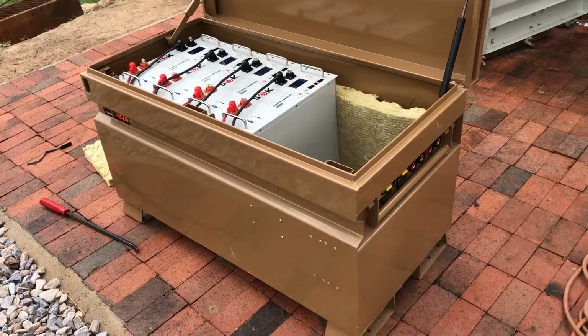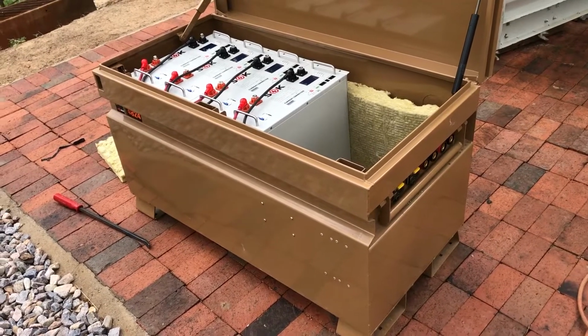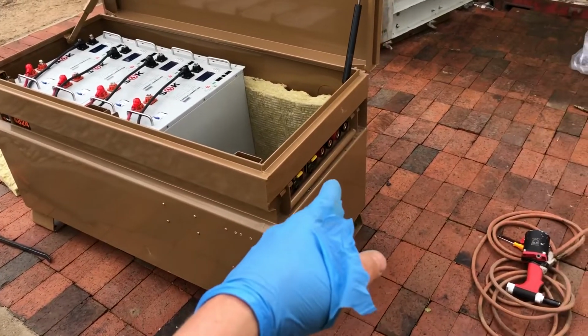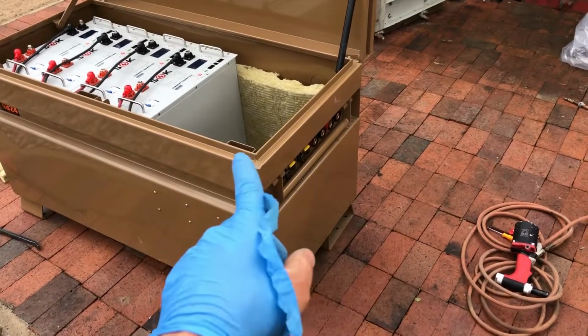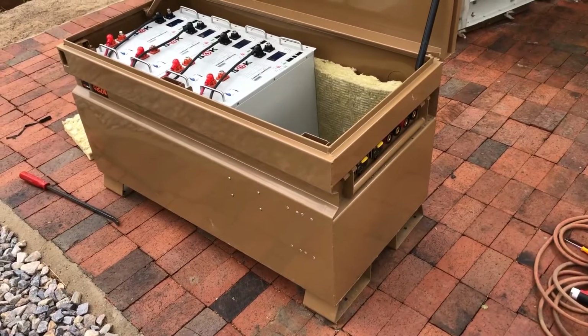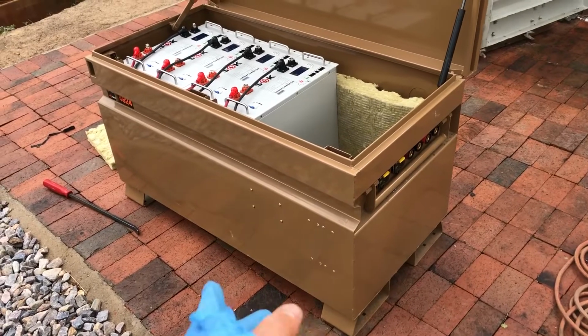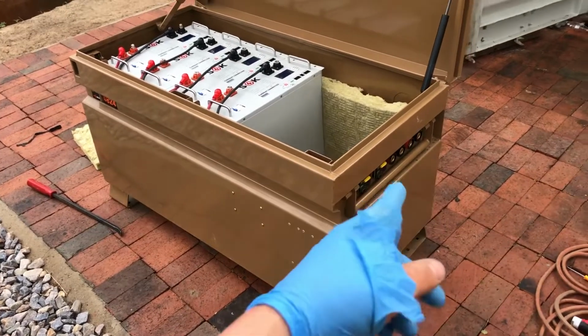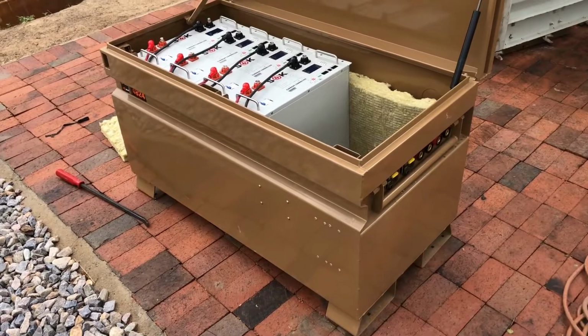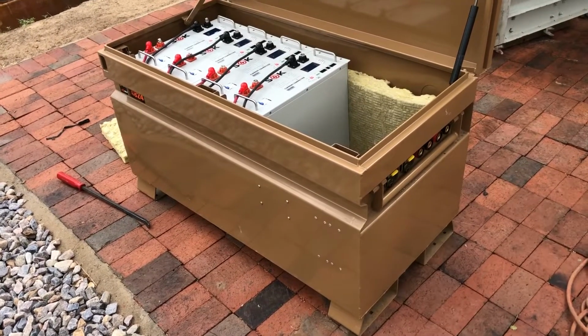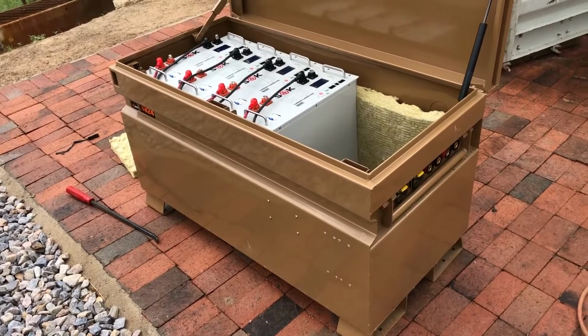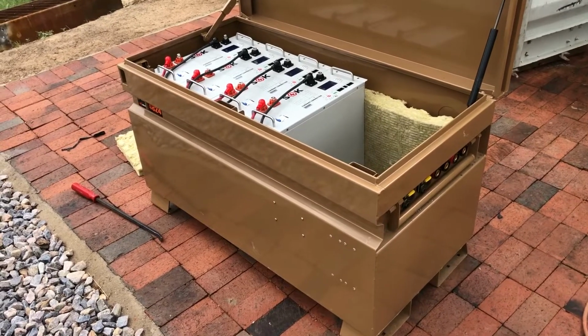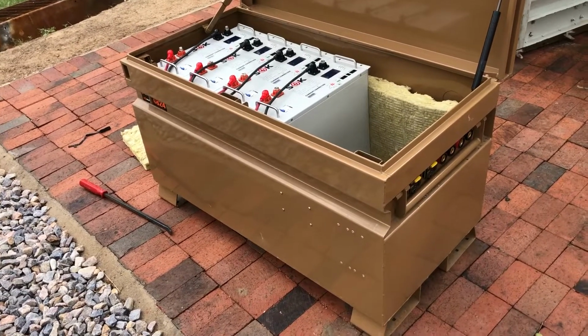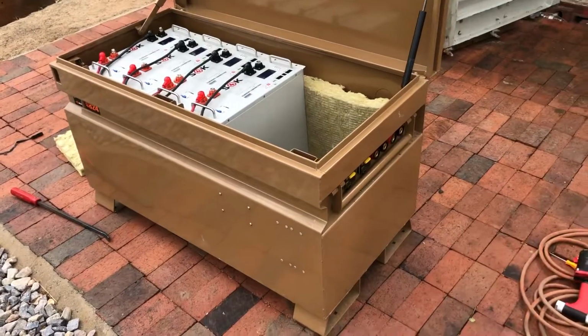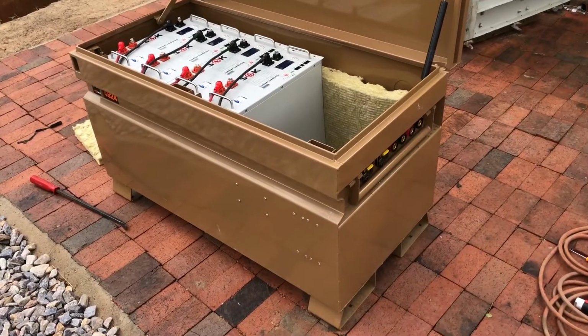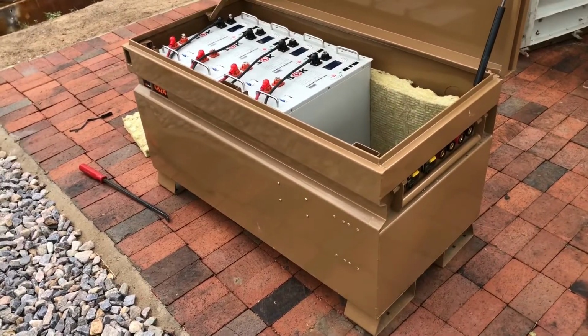I've been playing with the numbers. The biggest limitation for charging is the breakers and fuses running back from the chargers. The way I'll probably do it, I'll charge them on one set, which limits me to about 200 amps of charging. So if I did more than 3 charge controllers at 55 amps each, it's conceivable I could overcurrent one of these circuit breaker situations.